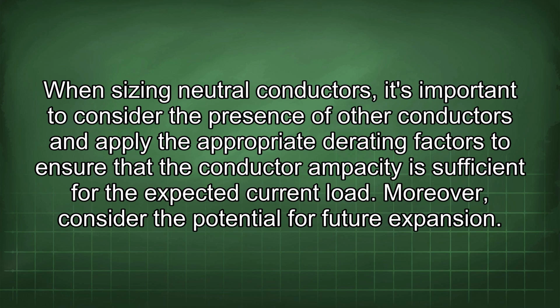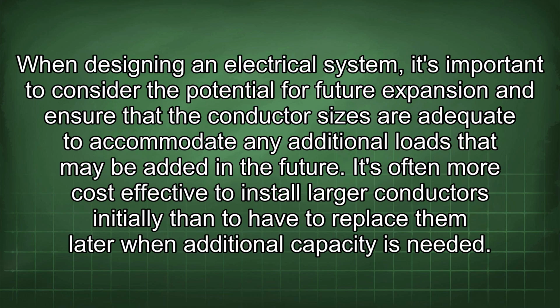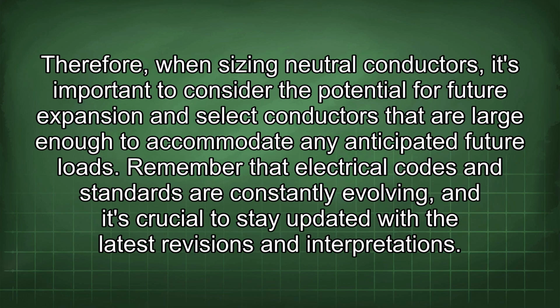Moreover, consider the potential for future expansion. When designing an electrical system, it's important to consider the potential for future expansion and ensure that the conductor sizes are adequate to accommodate any additional loads that may be added in the future. It's often more cost-effective to install larger conductors initially than to have to replace them later when additional capacity is needed. Therefore, when sizing neutral conductors, it's important to consider the potential for future expansion and select conductors that are large enough to accommodate any anticipated future loads.